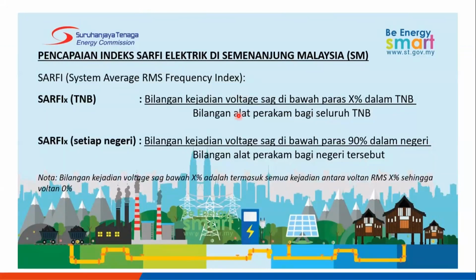Okay, so ST have come up with an index to measure the severity of voltage sag, called SARFI, System Average RMS Frequency Index. SARFI X means the percentage of voltage sags. Let's say SARFI 90. It is the number of voltage sag events below 90% in TNB, divided by the number of recorders, the recorded numbers. We have PQ recorders installed in our network, multiple PQ recorders. So it is divided by the number of power quality recorders that record voltage sag below 90%. And this is for the whole TNB.